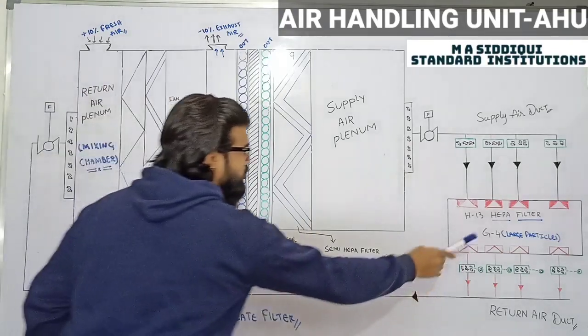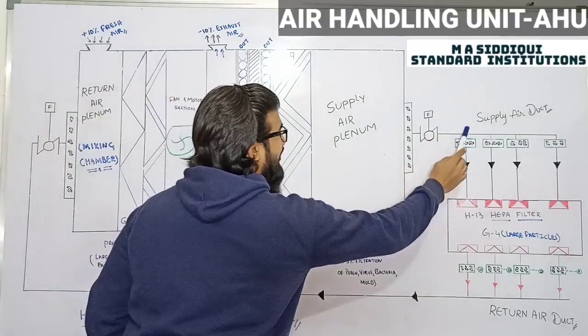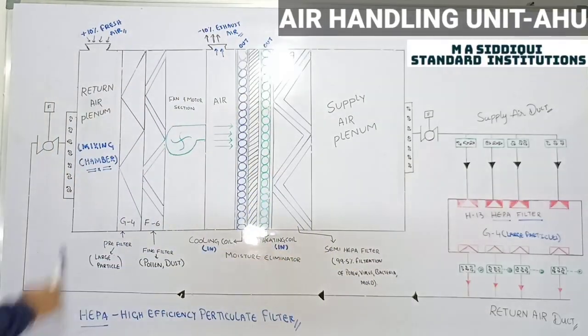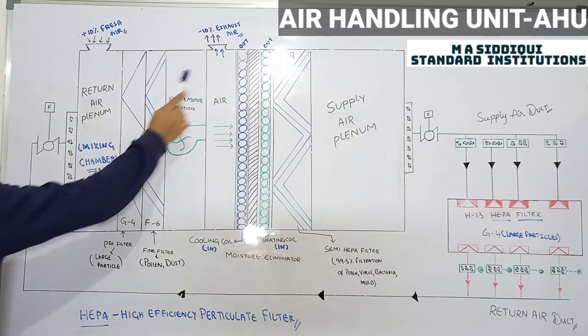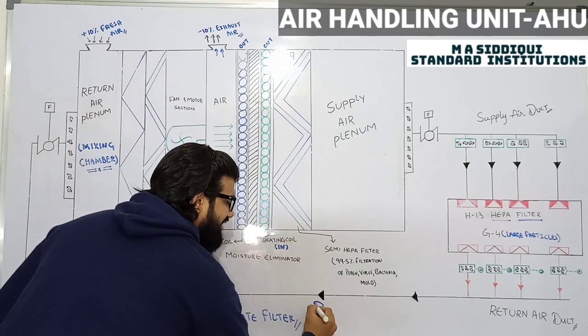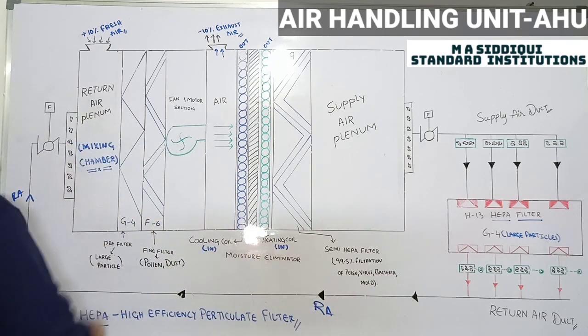Fine. So this is the huge air handling box. That's the space which has to be cooled. From here we will be giving cool air via supply air duct, and it returns through the return air duct. How? Let's study the box. The very first part of the air handling unit is the mixing chamber. Why am I saying mixing chamber? Because from here we are getting return air from the space. This return air enters into your mixing chamber.